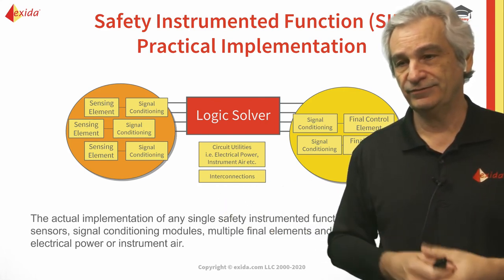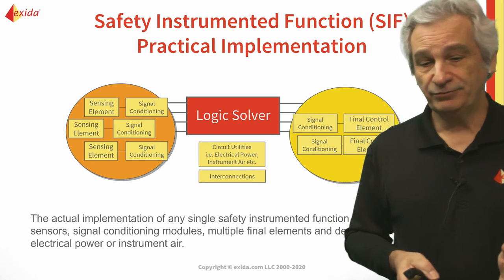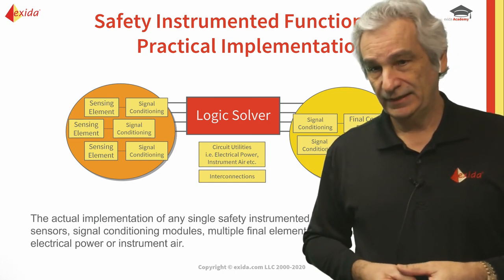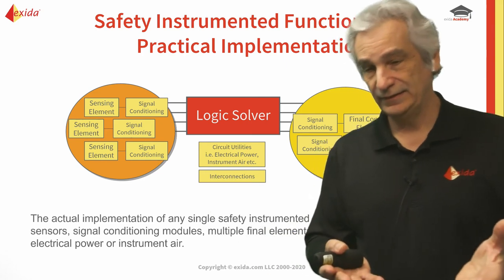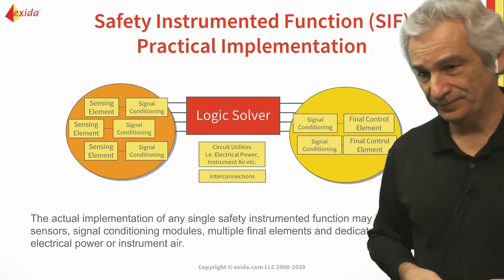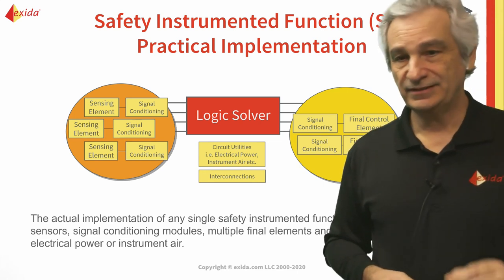People say to me: if I've got a SIL 2 sensor, a SIL 2 logic solver, and a SIL 2 final element, I have a SIL 2 SIF — don't I? Not necessarily. What you have to consider is that the SIF is tip to tail and everything in between. For example, if we've got Zener barriers, we have to include them. If we've got splitters, we include those. If we've got an interposing relay, we include the relay along with the sensor. From the logic solver point of view, we have to consider ancillary equipment — power supplies, communication links, etc. The same applies on the output side — signal conditioning and the final element itself, including any motor controller. All of that has to be considered as part of the SIF. That's why simply having SIL 2 rated components does not necessarily mean you'll achieve a SIL 2 requirement.